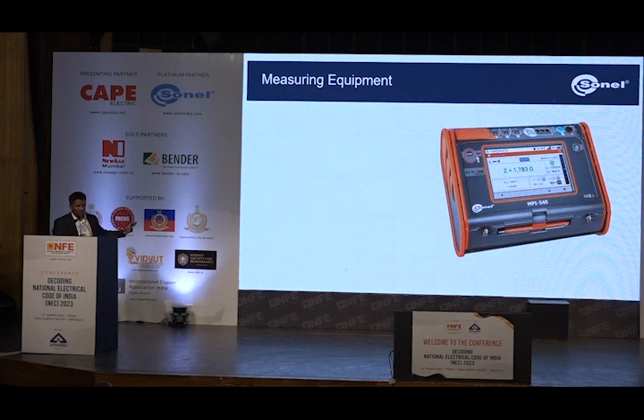The previous ten testings, whatever has been shown, we try to bring all this into one equipment, which includes soil resistivity, earth resistance, loop impedance measurement, RCD tripping time, tripping current, and power quality analysis. The same equipment you can take to an EV charging station, and also to a solar panel application.